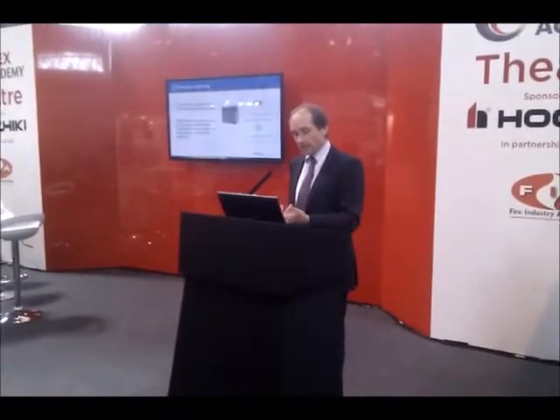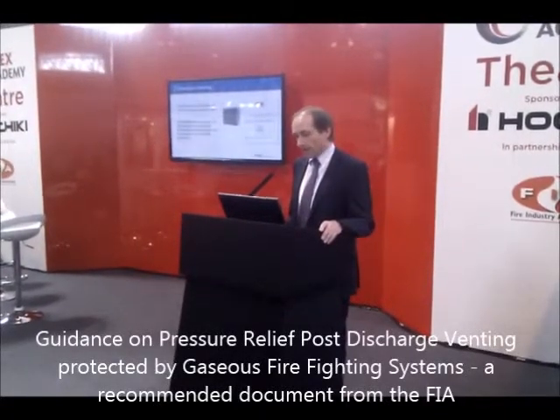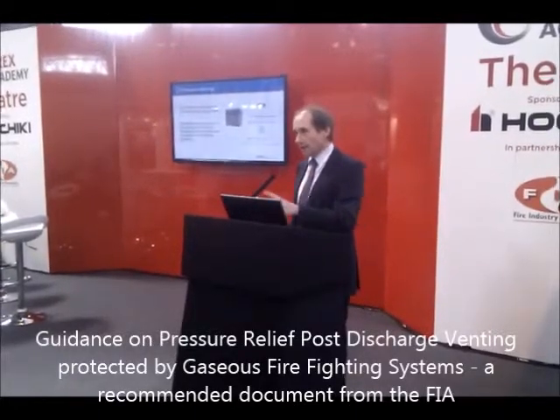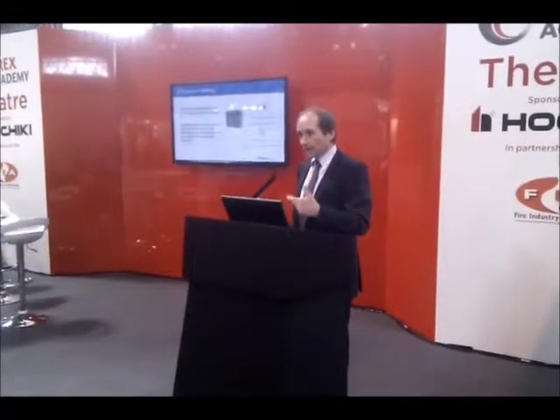For detailed calculations for venting requirements, you can refer to an FIA publication — guidance on the pressure relief and post-discharge venting of spaces protected by gaseous firefighting systems. That's a very good reference document that identifies how you calculate pressure vent requirements, the various conditions, and the types of vents and devices that you may find.